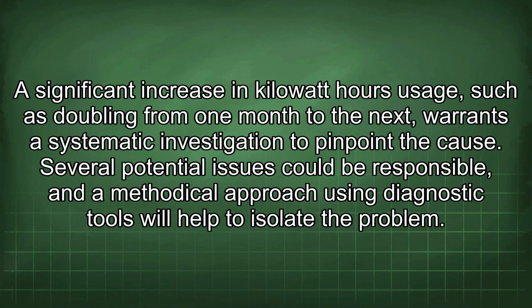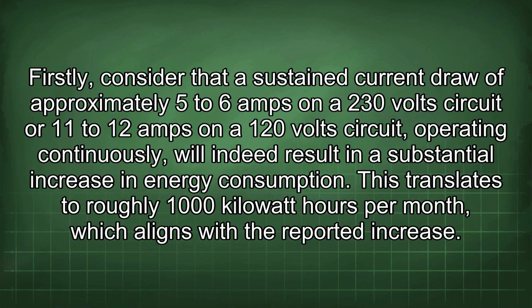A significant increase in kilowatt-hours usage, such as doubling from 1 month to the next, warrants a systematic investigation to pinpoint the cause. Several potential issues could be responsible, and a methodical approach using diagnostic tools will help to isolate the problem. Firstly, consider that a sustained current draw of approximately 5 to 6 amps on a 230 volts circuit or 11 to 12 amps on a 120 volts circuit, operating continuously, will indeed result in a substantial increase in energy consumption. This translates to roughly 1,000 kilowatt-hours per month, which aligns with the reported increase.